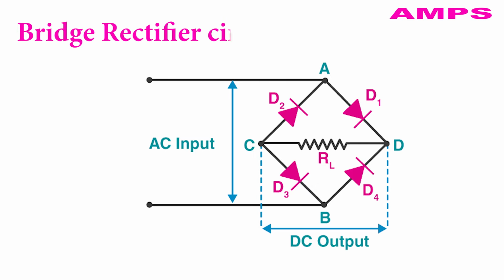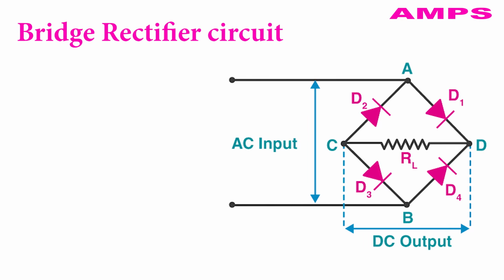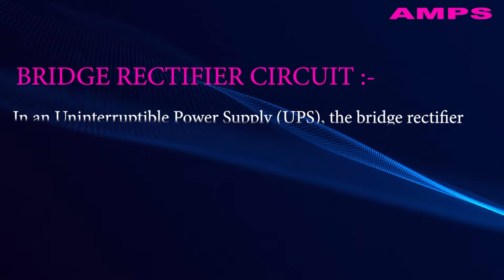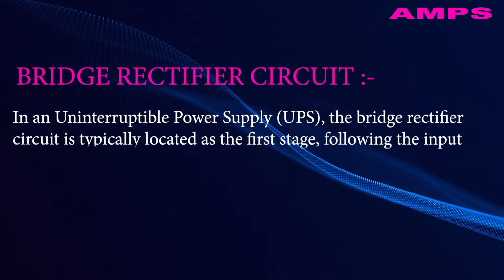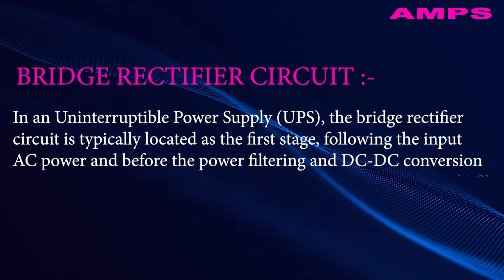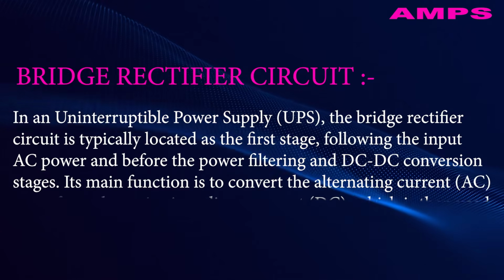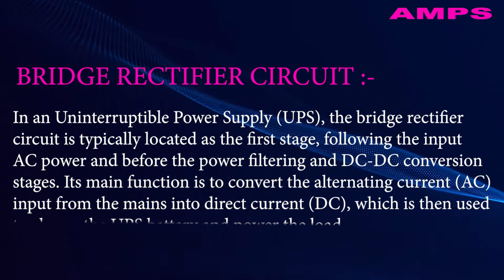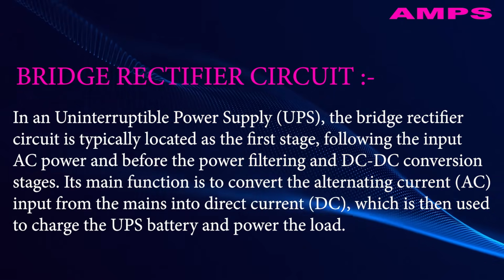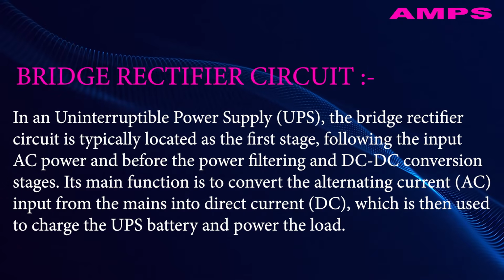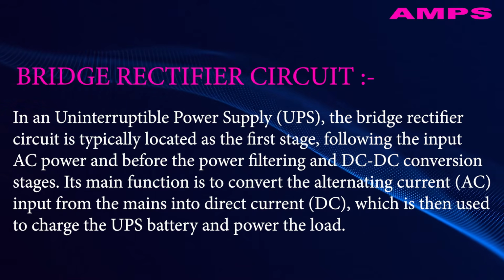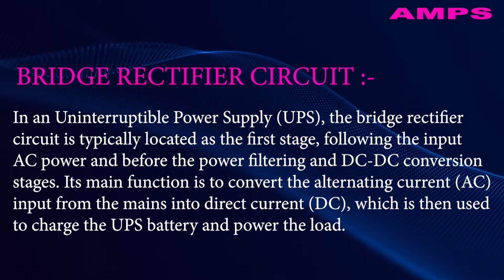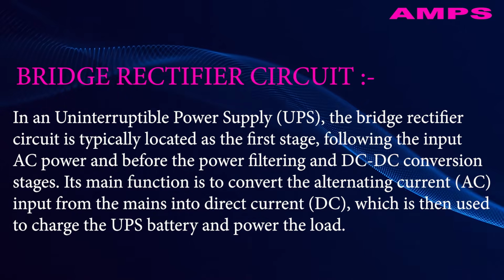Bridge rectifier circuit. In an uninterruptible power supply, UPS, the bridge rectifier circuit is typically located as the first stage, following the input AC power and before the power filtering and DC to DC conversion stages. Its main function is to convert the alternating current, AC, input from the mains into direct current, DC, which is then used to charge the UPS battery and power the load.